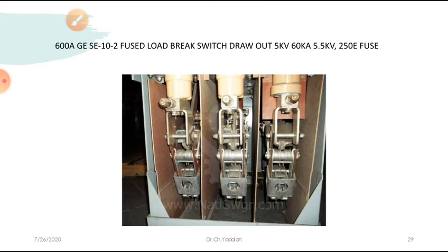Once ionized, a path is formed through which electrons will try to flow and continue the circuit. These electrons collide with the air particles, and then a big arc takes place. That arc has a high temperature that may melt the two tips of the contacts. So to avoid that, we use different quenching medias, by splitters, by lengthening, by cooling; different methods are used.